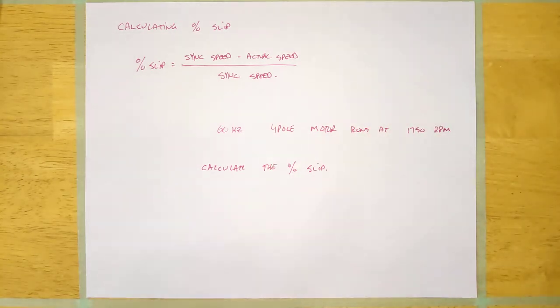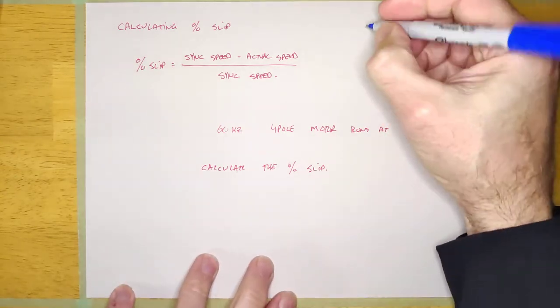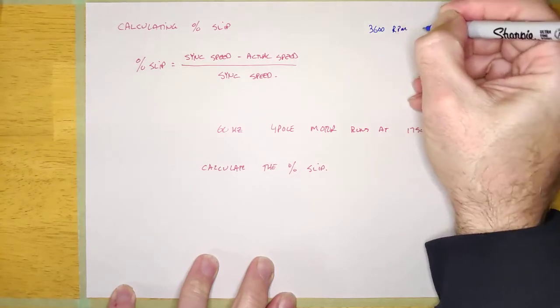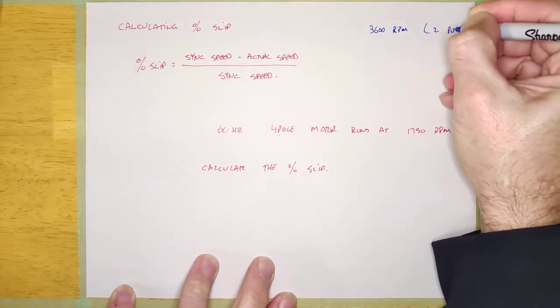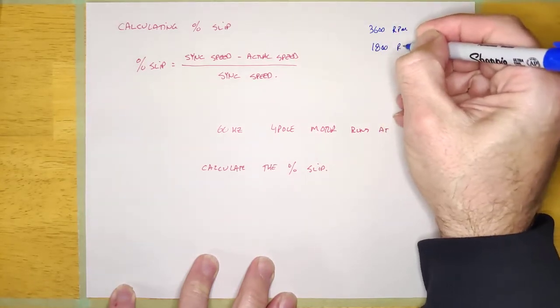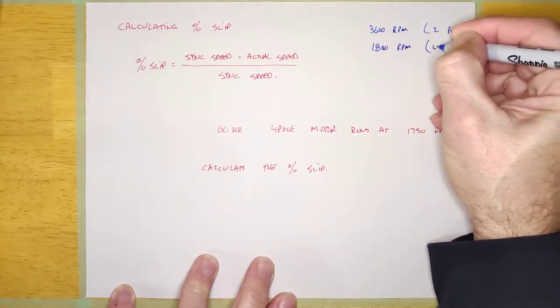But I want you to remember that there's only two sync speeds in real life at 60 hertz. And one is 3,600 RPM, which means it's a two-pole, and one is 1,800 RPM, which is a four-pole.